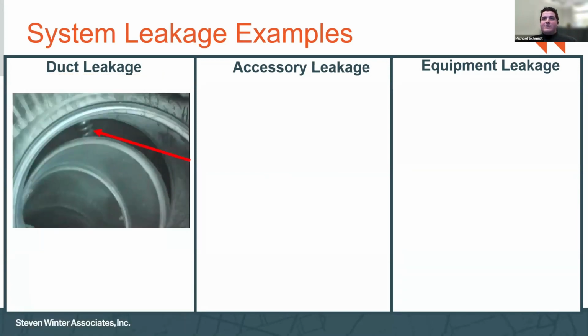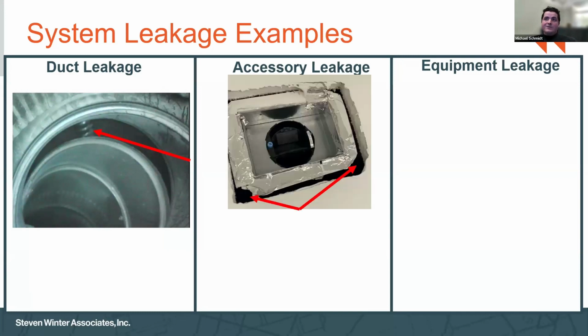What else can we see in duct leakage? This is actually a shot from the inside of a duct using a borescope during the commissioning and balancing process. There was an issue with getting exhaust flow rates on a specific branch of the duct. And here we can see, this picture speaks a thousand words, right? We assume the electrician was pulling a wire through and had broken off the ductwork behind the wall. Walls got closed up, and of course we weren't getting any flow rates. So there are things that can happen to a fairly well sealed duct system after the fact, right? That can also impact duct leakage.